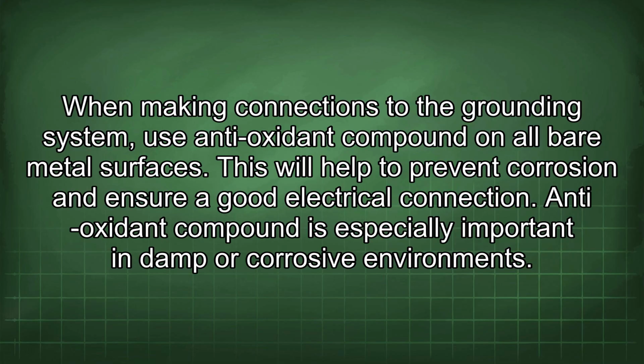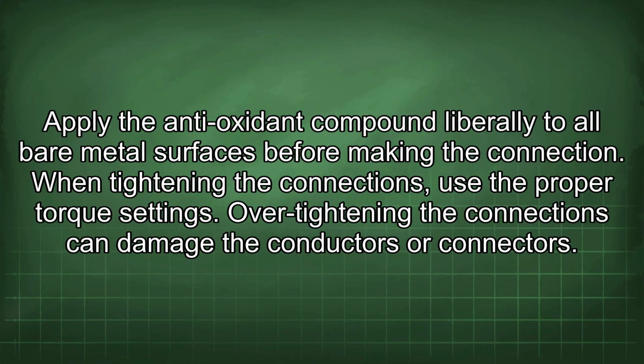This will help to prevent corrosion and ensure a good electrical connection. Antioxidant compound is especially important in damp or corrosive environments. Apply the antioxidant compound liberally to all bare metal surfaces before making the connection. When tightening the connections, use the proper torque settings.